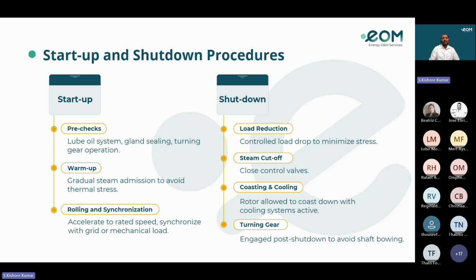Skipping the startup and shutdown checklist and bypassing the alarms leads to catastrophic failures in the turbines. Always follow the startup curves during cold and hot startups, and ensure every permissive is satisfied. If any of the permissives is overridden, that will cause differential temperature, lead to rotor deformation, and cause major damage in the turbine.